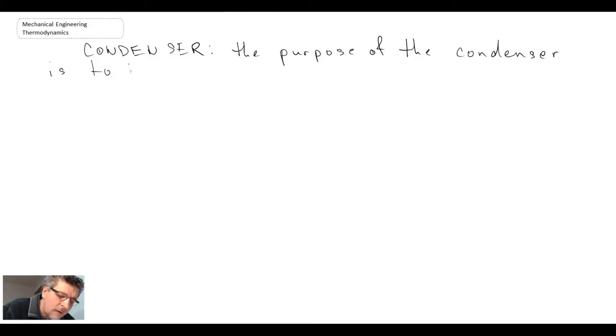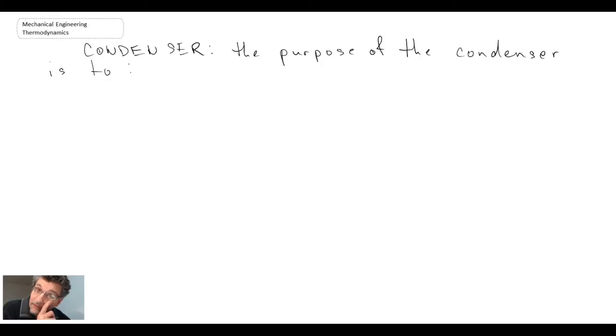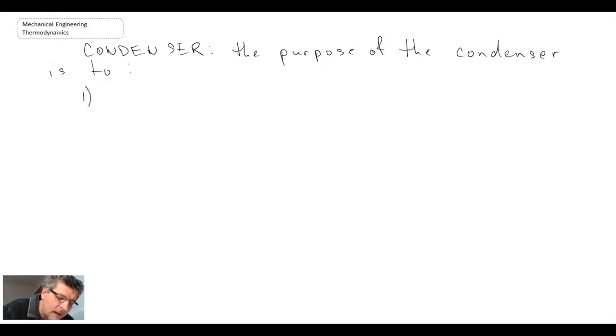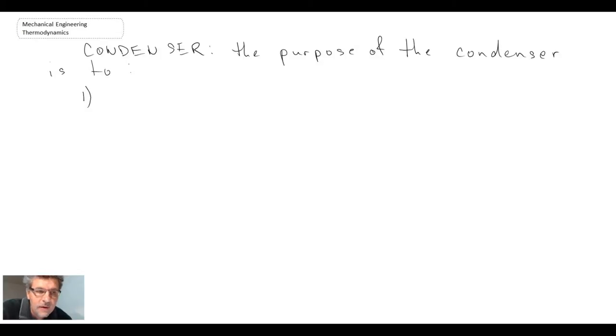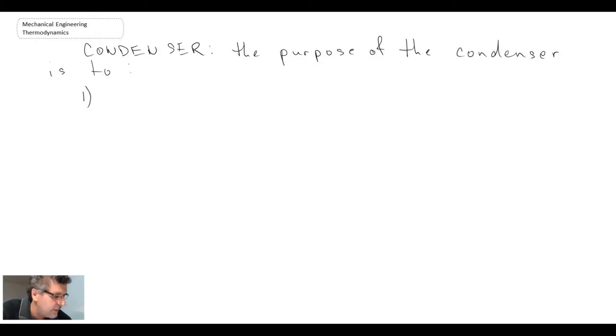So the purpose of the condenser, there are actually a number of different purposes. One of them is we want the condenser to be operating at a low pressure and that is the pressure at which we expand the steam in the turbine to.